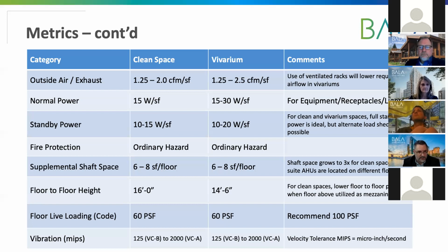Similar to a typical lab, the fire protection, the shaft space, even the floor-to-floor height is pretty similar. And again, we can work with less than 14.5 feet, but that's the ideal. And then, as Steve mentioned on the previous slide, the structure was pretty similar for these spaces. The only thing I want to mention was the vibration. The vibration is another stressor for animals. They will be very sensitive to that, and they can pick that up, even if it's at a level that we can't feel or sense. So it's important to make sure where the animals are housed is very low vibration. Again, as Steve mentioned, there are techniques you could apply where you just stiffen the steel, say in the area where the animals are housed. So it's not for the entire area of the vivarium, it would really just be where the animals are housed. Okay, next slide.